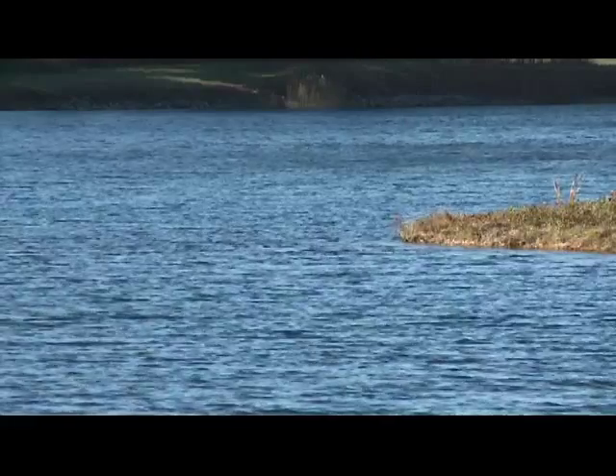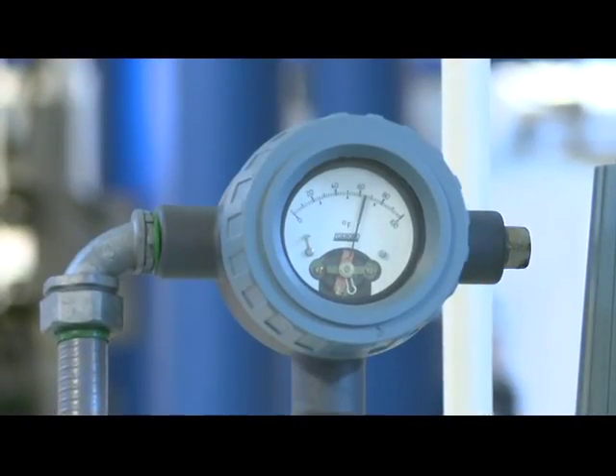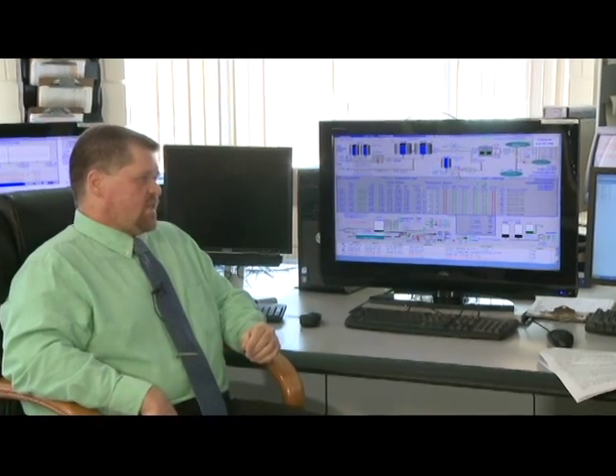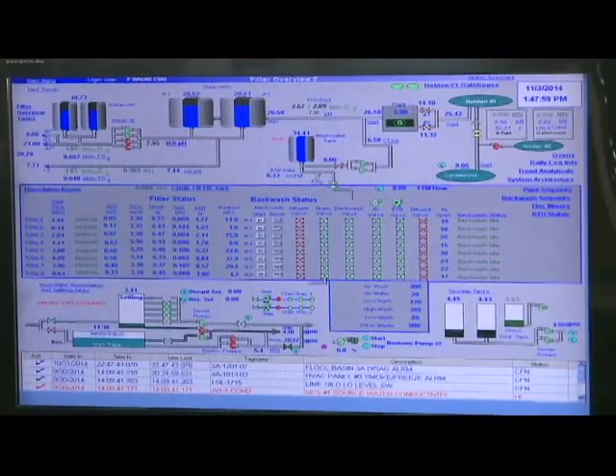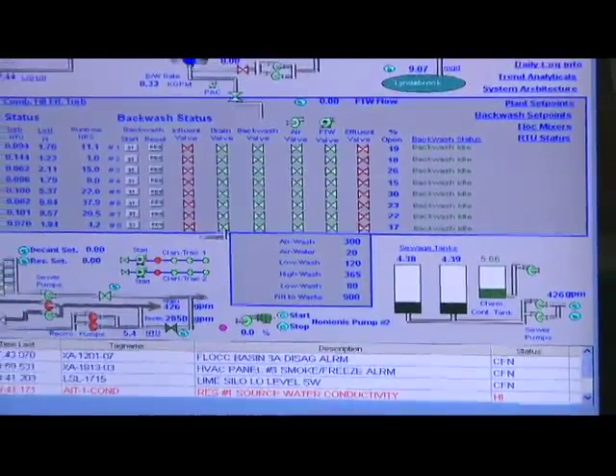In this control room, you can monitor what's going on at any given place — not only here at the filtration plant, but also if there's a valve leak or pipe break somewhere in the city. This is what allows us to get by with only two water filtration plant operators on staff 24-7. This is called a SCADA system — supervisory control and data acquisition. All the instrumentation data from around the filtration plant is brought up here, right at our fingertips. We have trends on screens that show us at a glance if something is departing from a normal operating parameter, and tank levels around the city show us which pumps are running.